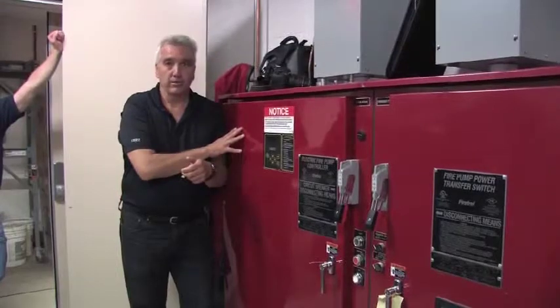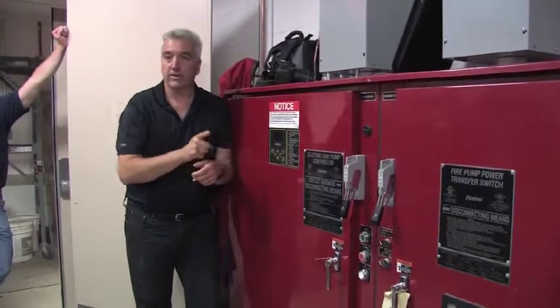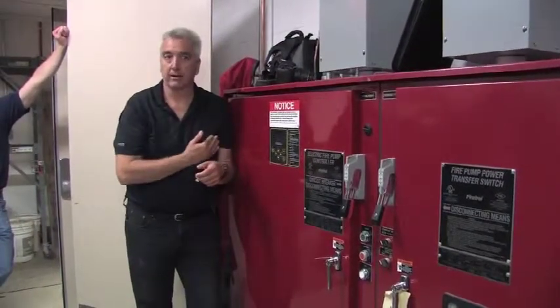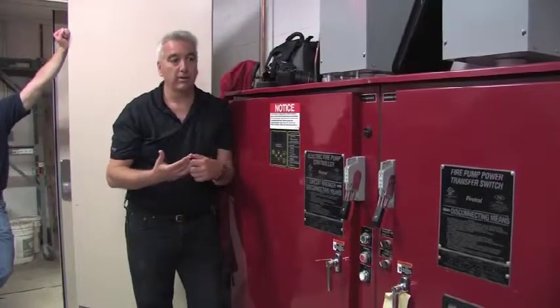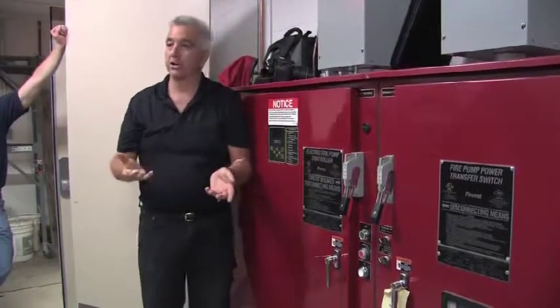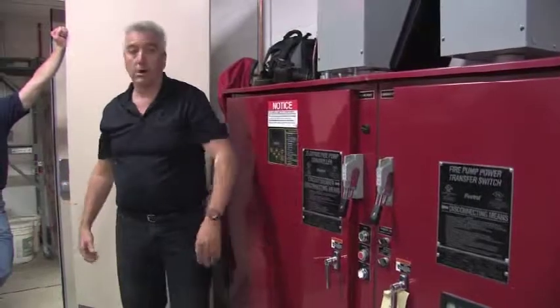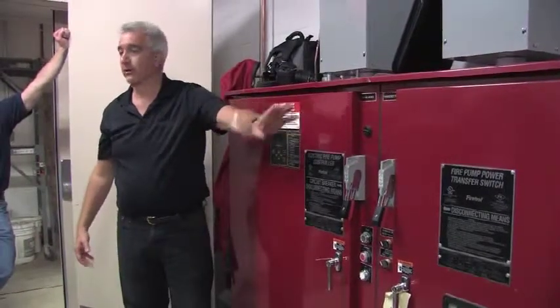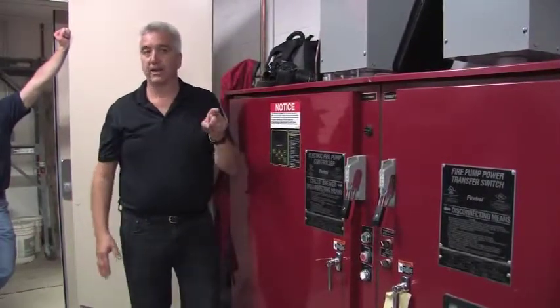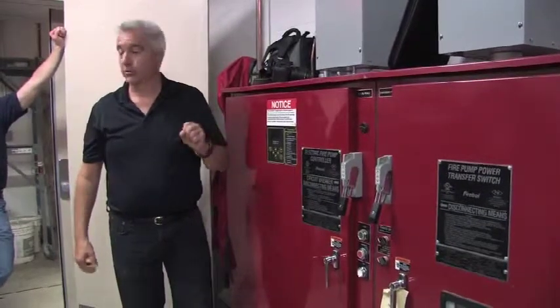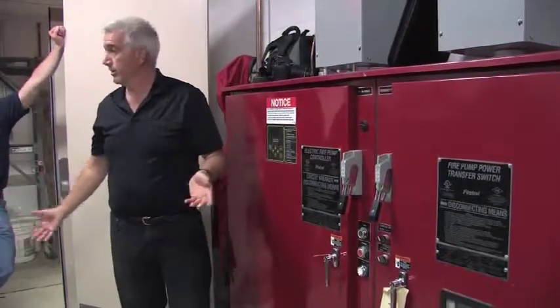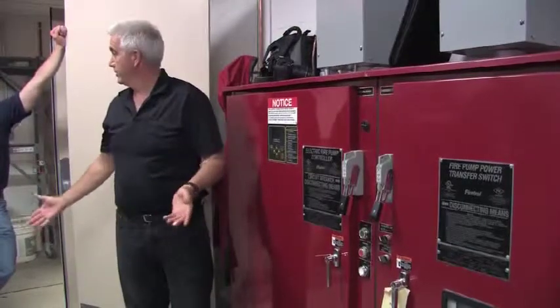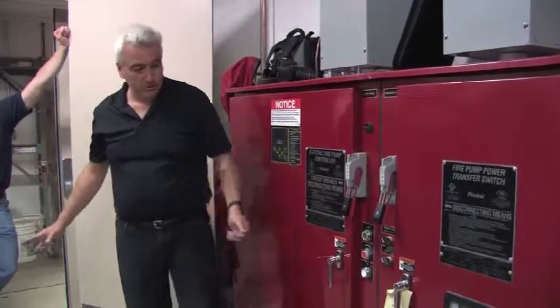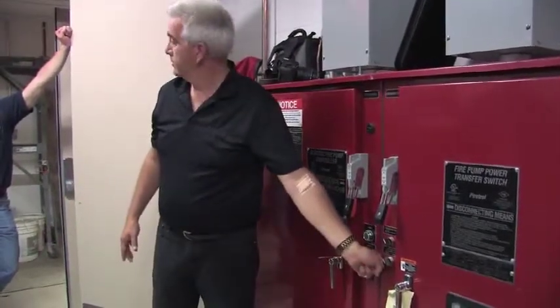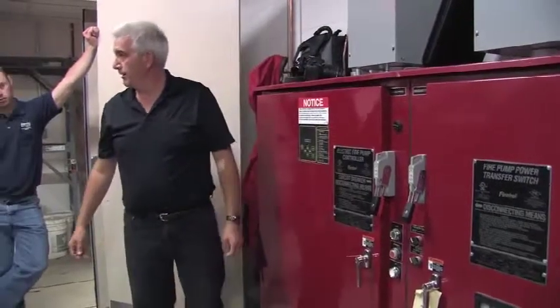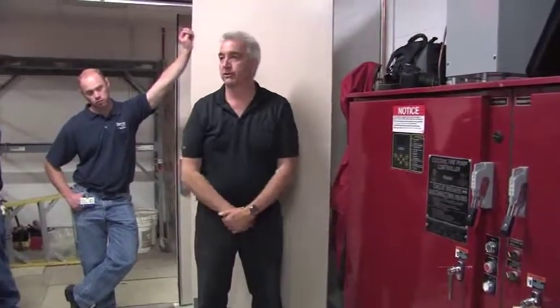If power is restored, then the controller waits 30 minutes before it switches back. That's an NFPA 20 code. A lot of the transfer switch people will go through and do a coordination check for a new building like this one and say, oh, you've got to change that back to 10 minutes, like all the others. Don't let them tell you that. By code, that has to be 30 minutes. Now, you can short circuit that. If you don't want to wait the 30 minutes, you can transfer it back as soon as you want with this switch right here. Switch right back to normal. But if it was left on its own, it'd be 30 minutes.